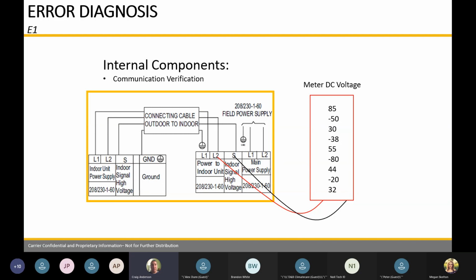So typical operation, you're going to see your DC voltmeter go from a minus 30 up to plus 50. It's going to go minus to positive, minus to positive. If you're testing it and it's staying in the positive, that's telling us we have something going on with our outdoor board. If your voltage reading is staying in the negative, that's telling us something's going on with the indoor board. But if we're getting a positive to a negative, that's telling us we're getting some communication, something else is going on.